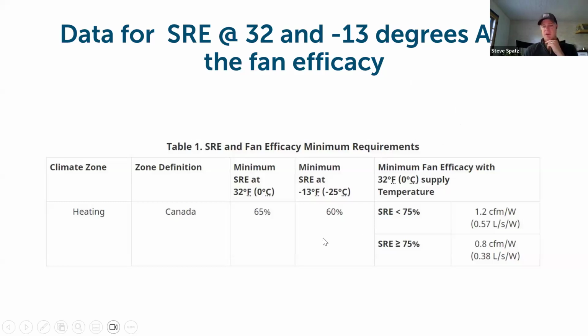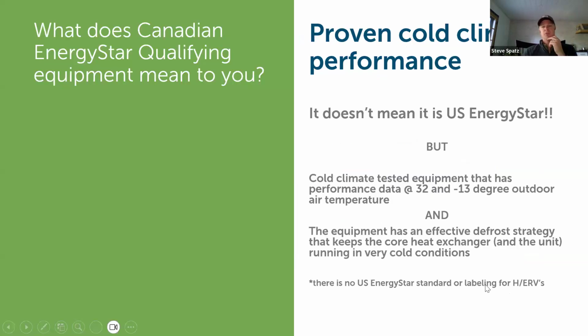These requirements here are showing the SRE of the equipment at -13 outdoor temperature and at 0 degree outdoor temperature as well. In HVI, you can see that data if it's available from the manufacturer. And what the Vermont RBES is calling out specifically is SRE at 32 degrees. But the Canadian standard is requiring manufacturers to prove that the equipment is working below 32 degrees and all the way down to -13 if they have tested it at that outdoor ambient temperature. This is also giving you CFM per watt at the different SREs and at the 32 degree outdoor temperature. So this Canadian listing is a valuable tool to consider when you're specifying your options for ERVs or HRVs in a new build.